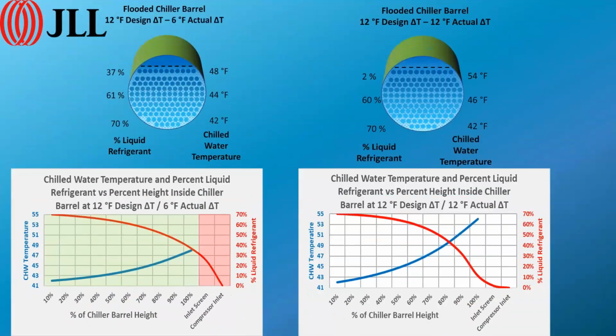And so you can see that here on the left, with a low delta T, 6-degree delta T on a design of 12, it's losing probably about 30% of its refrigerant charge and refrigerating effect at the inlet screen. That's a lot. You lose 30% of a 1,000-ton chiller, you only have a 700-ton chiller, and it's just blowing it right at the inlet screen. So we don't like that. We don't like to see that.